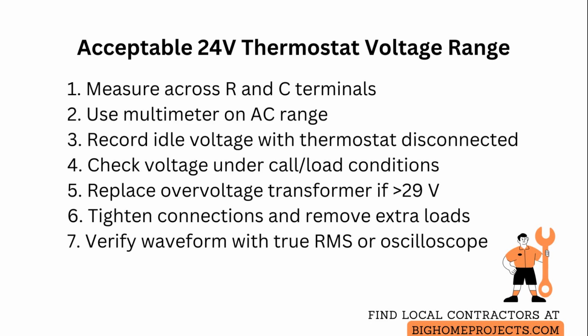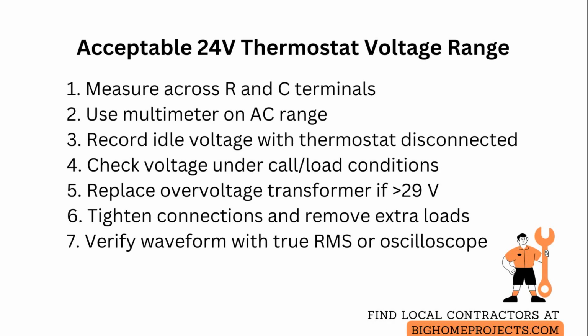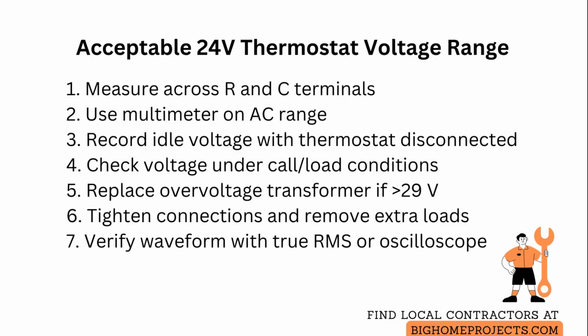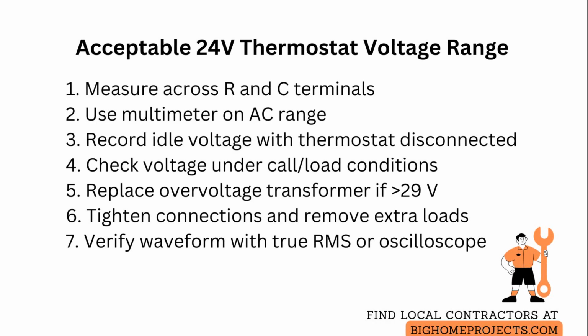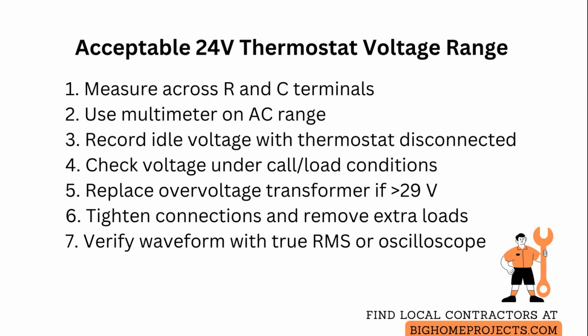If readings fall below 24 volts alternating current, inspect for loose or corroded terminal connections, excessive load from added accessories, or a weak transformer winding. Tighten connections, remove non-essential loads for testing, and consider transformer replacement if low voltage persists.